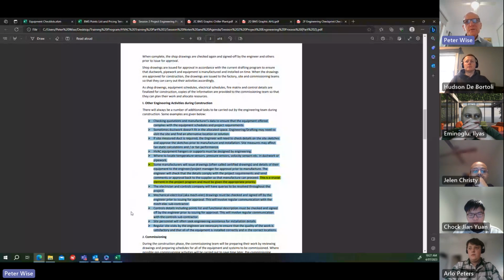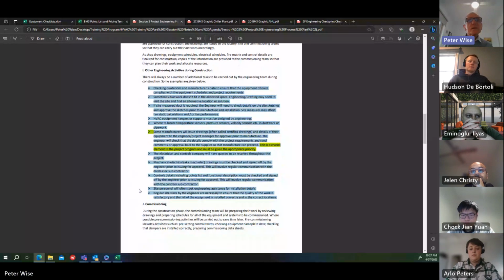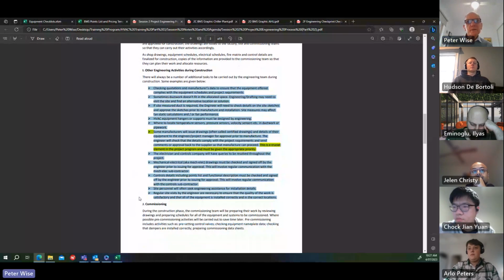Controls details, including points list and functional descriptions, need to be checked off and signed off by the engineer prior to issuing for approval. Again, communication with the controls people. Site personnel will often seek your assistance during the installation of the work. So they may not be sure of what's got to be done. They'll call you. You might have to go to site and help them resolve that. Regular site visits by the engineer are necessary to ensure the quality of work is satisfactory and all the equipment is installed correctly and in the correct locations.